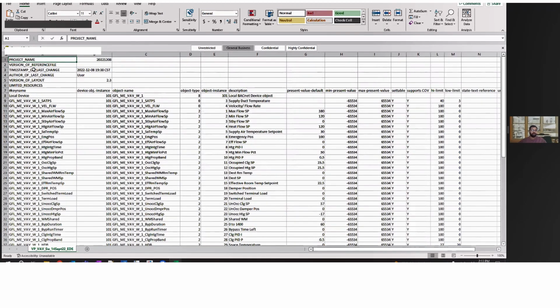So if we go to the EDE, it has the standard name, what date it was taken, and so on. Then the point name, local device, object instance of the controller, object name which is the point name, and object type. This is how the points are defined in the BACnet world.